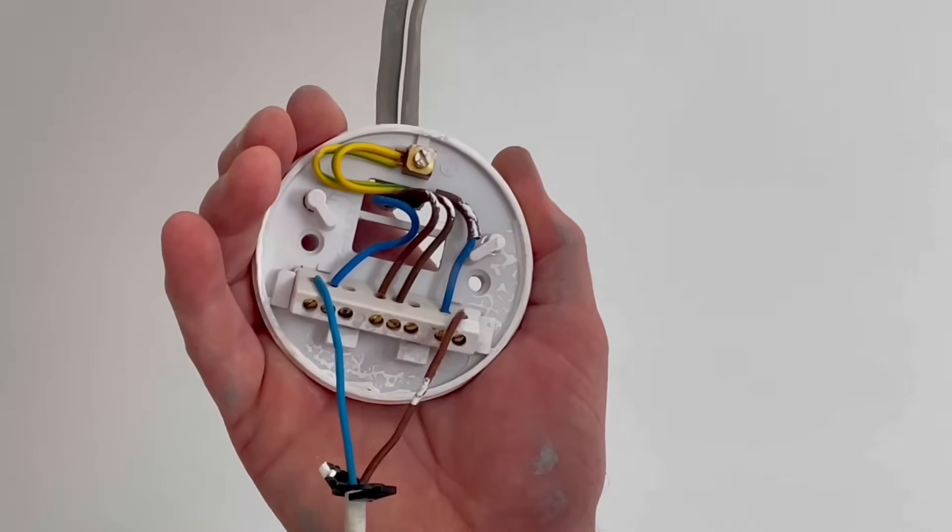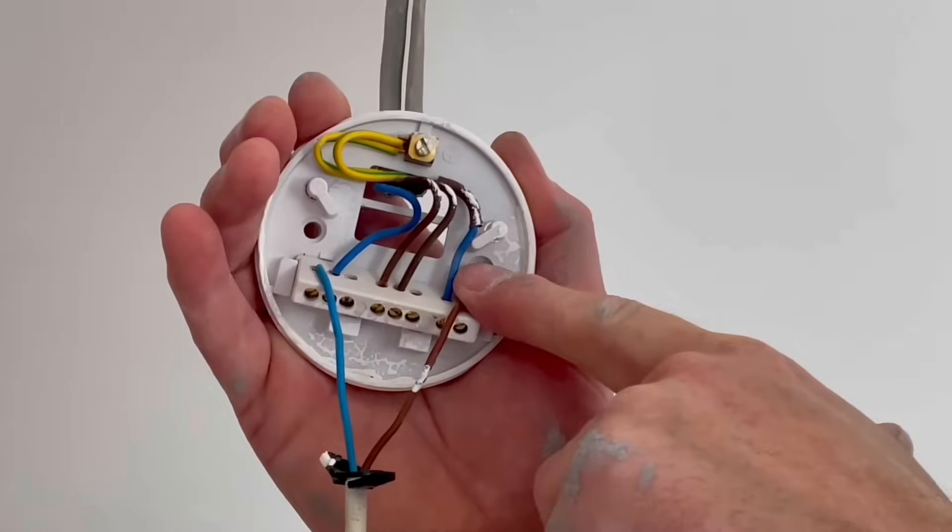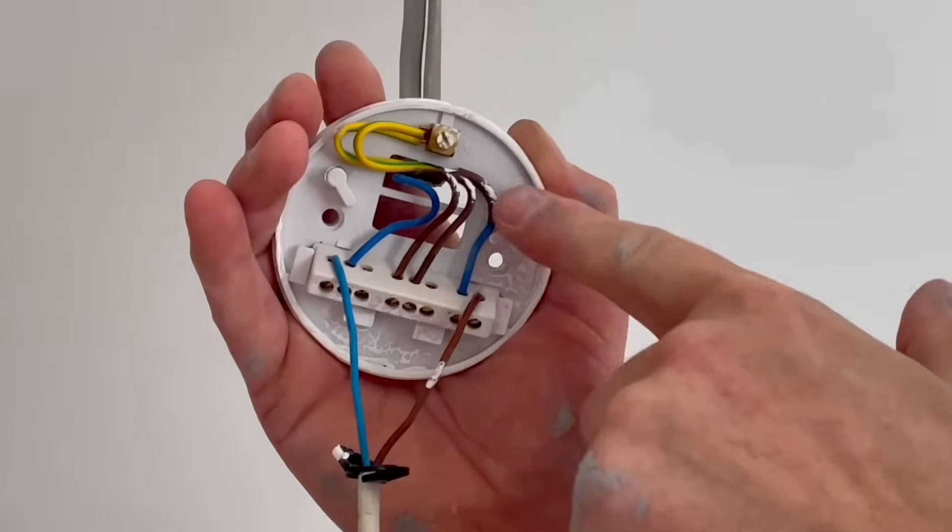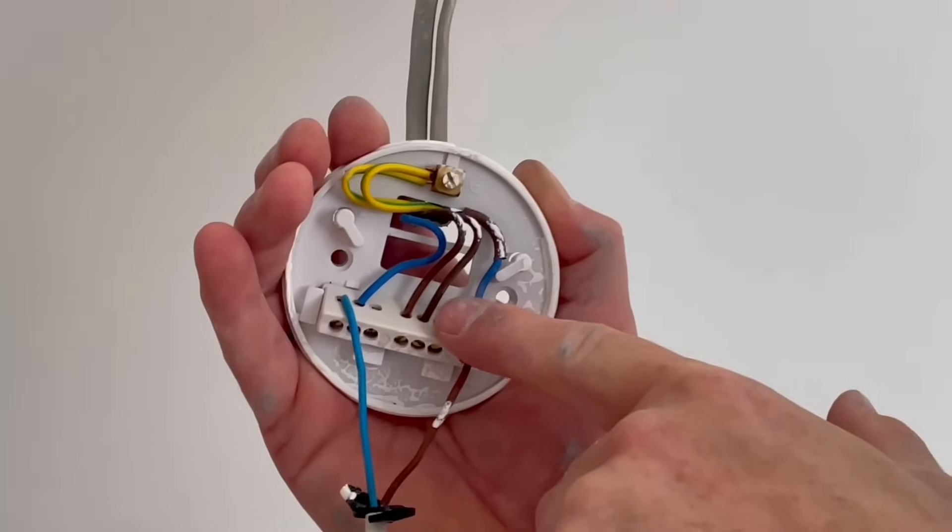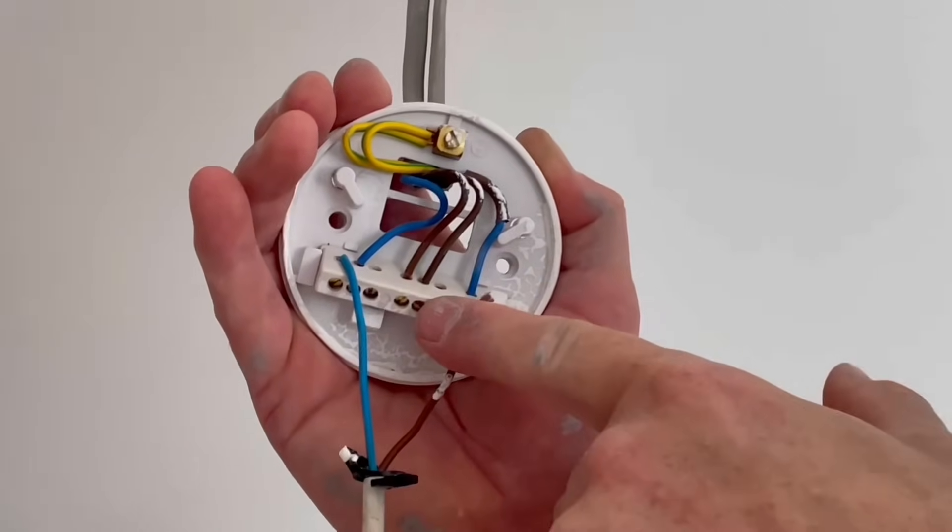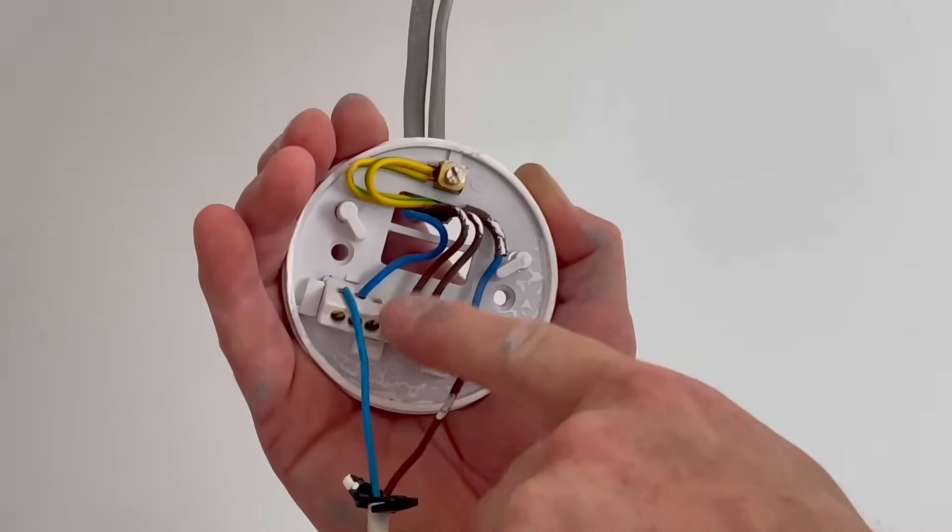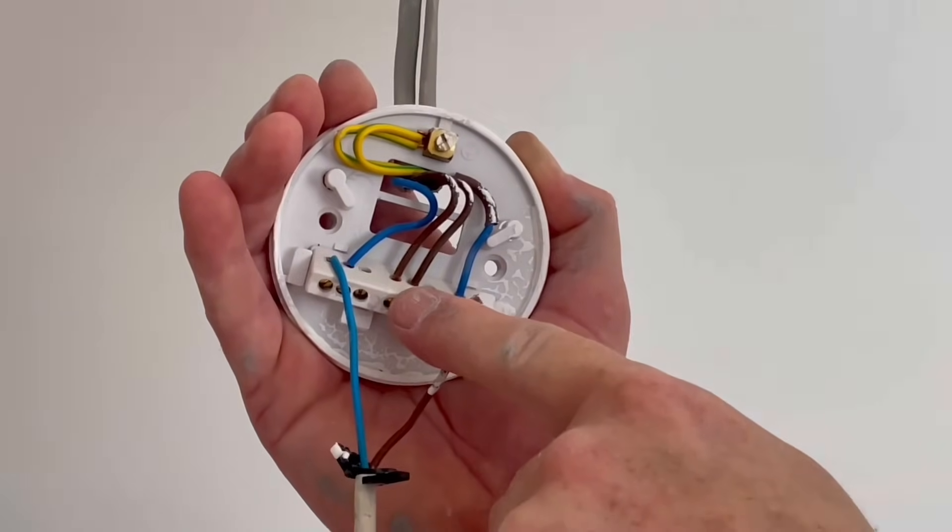This side here we've got the brown conductor coming down to our pendant with a blue conductor next to it but note it's got some brown sleeving so that is actually not a neutral, it's a switching line conductor. It comes in with a permanent line conductor which is in loop and a CPC. We've also got the permanent line, neutral and CPC which brings our power supply in.